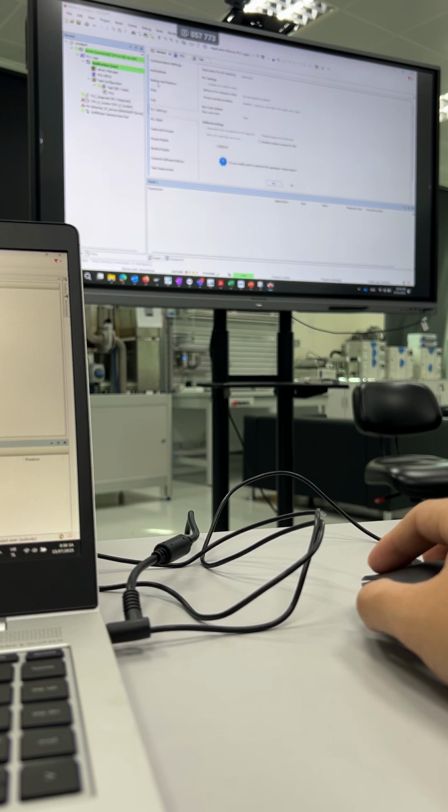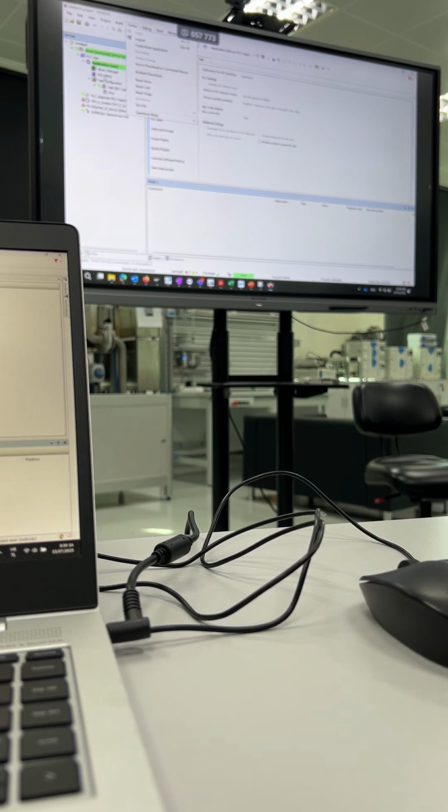When you reset warm, the mode will change to stop, and then you can just start it again. But reset origin means that you will delete everything inside the PLC. Not really a new PLC, but the program will be gone. What you have downloaded here will all be gone. Your IP address and everything else will still remain.